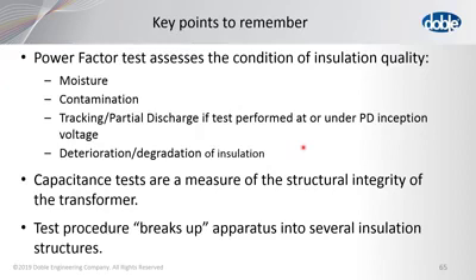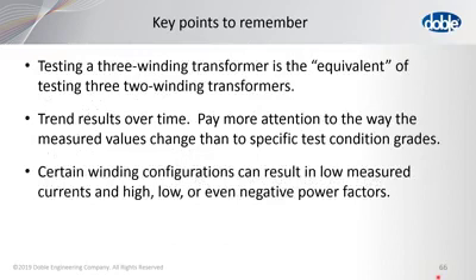Now, the test procedure breaks up the apparatus into several insulation systems. What we mean by that is, let's say for tests 1, 2, and 3, we have CH plus CHL, and then we break it up so that we measure CH separately and then CHL separately. So each one of the smaller insulations is tested. A key point to remember is that testing a 3-winding transformer is the equivalent of testing 3 2-winding transformers. Remember, the procedure is all in DTA, so it's difficult to do it incorrectly.